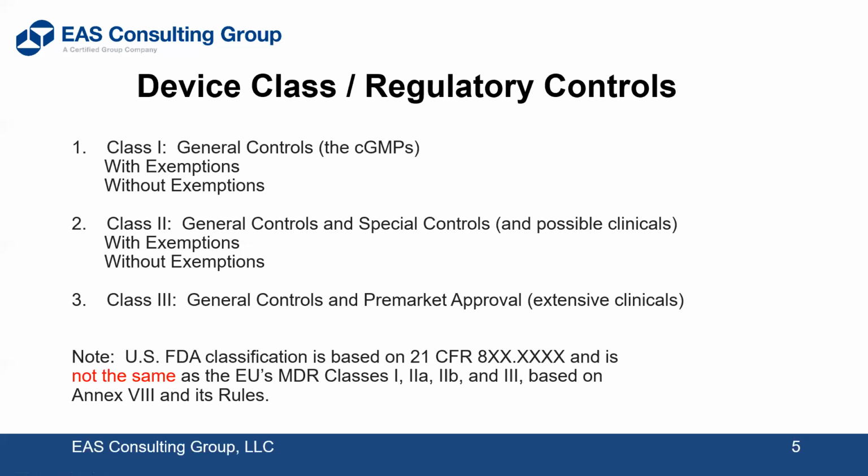Another difference between Europe and US: when you're dealing with a 510K, you submit a lot of information about the product, and then they review that, they may request additional information, and finally they clear it, then you can go to market with the product. Later on, maybe a year or two later, they'll show up at your door and do a compliance inspection. In Europe, you have to go through all the certifications and inspections before you go to market, before you're going to affix the CE mark.